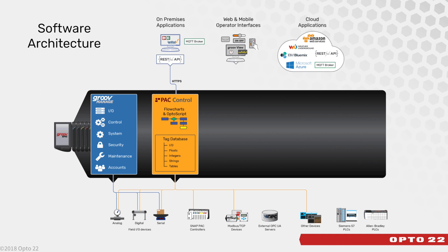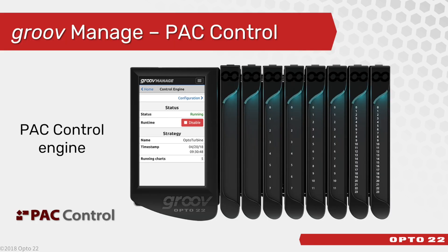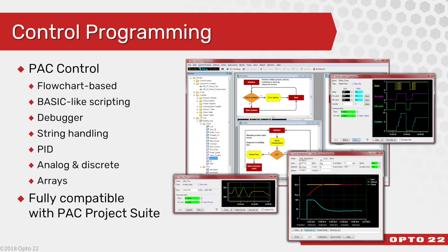With PAC Control, it's here where we create our tag database and we create our flowcharts and scripting for our control strategy. Within groov Manage, you can view the status and configuration of the control engine running directly on the Epic controller. Our free PAC Control software development tool has been around for decades, offering the simple elegance of flowchart-based control with up to 64 simultaneously running charts, plus sophisticated scripting for advanced programmers, all coupled to a real-time visual debugger. Support for analog, digital, and string handling remains, plus PID control loops and arrays of many types.